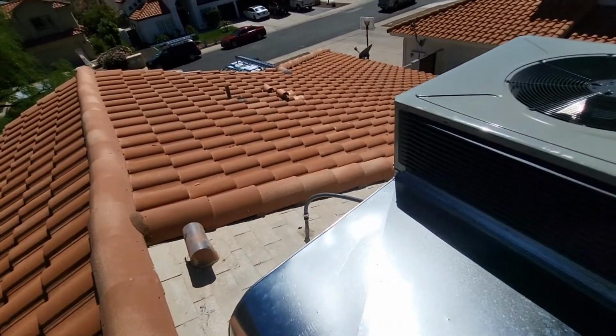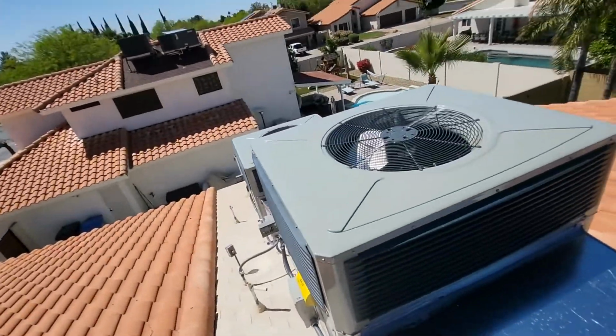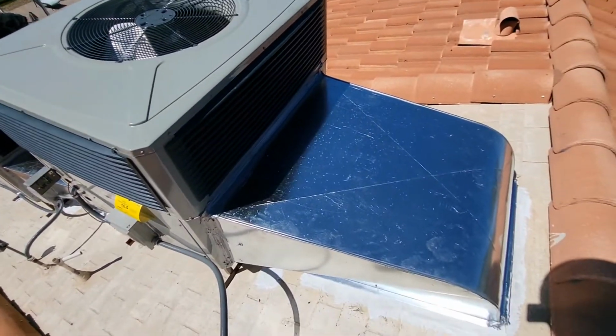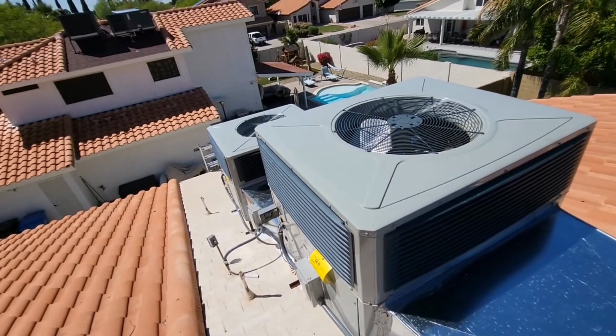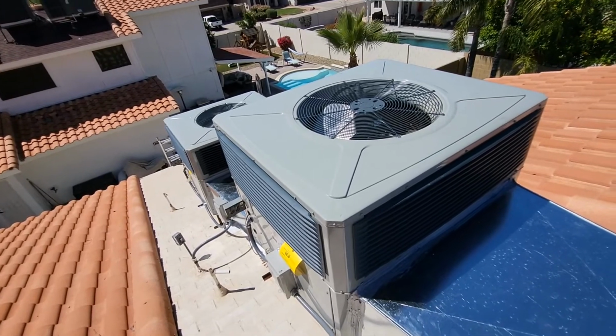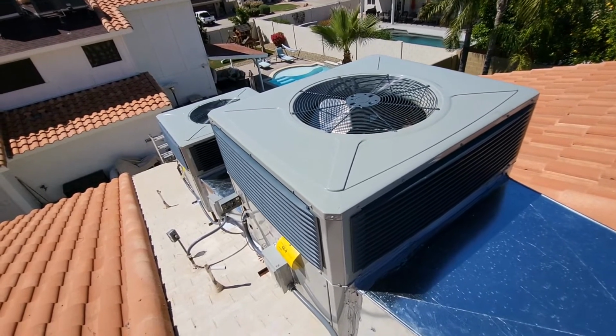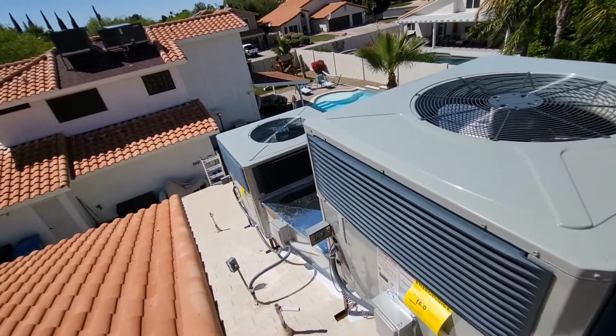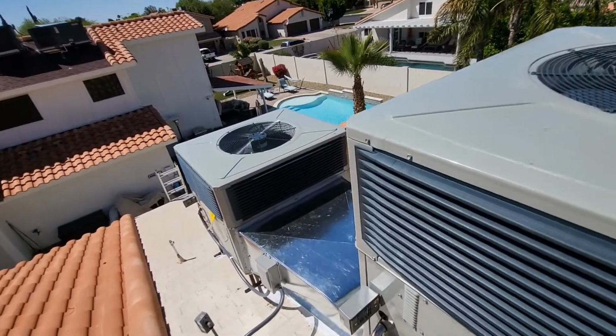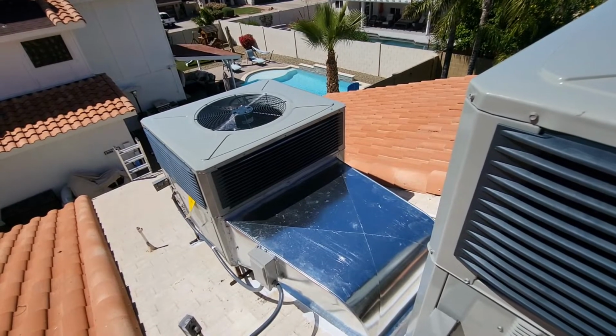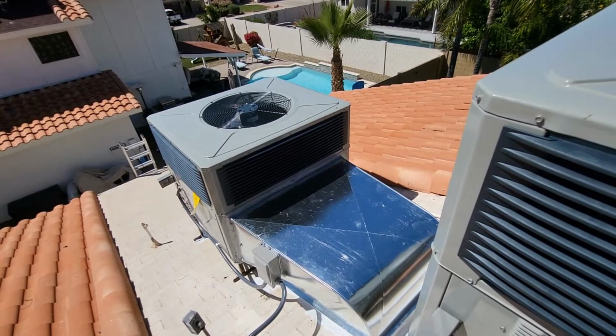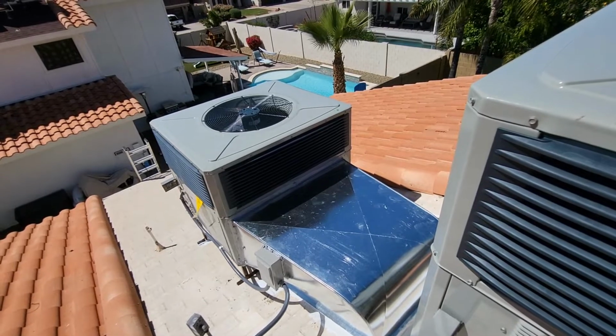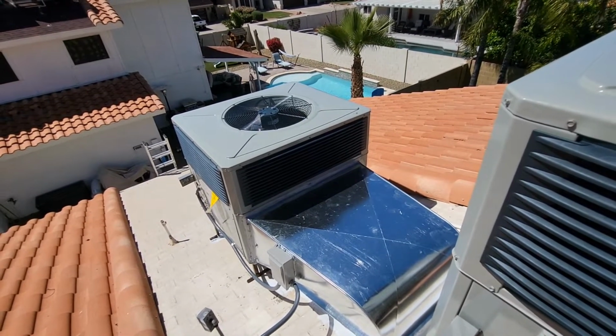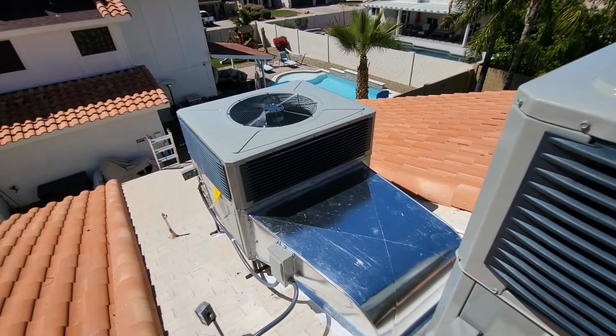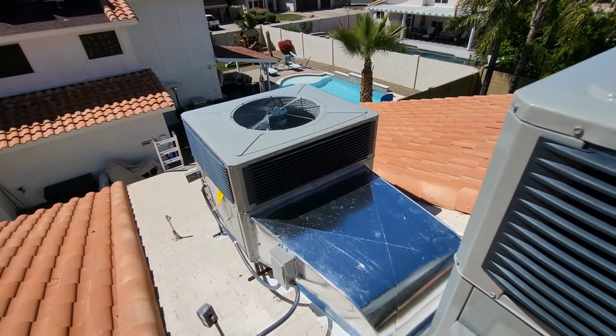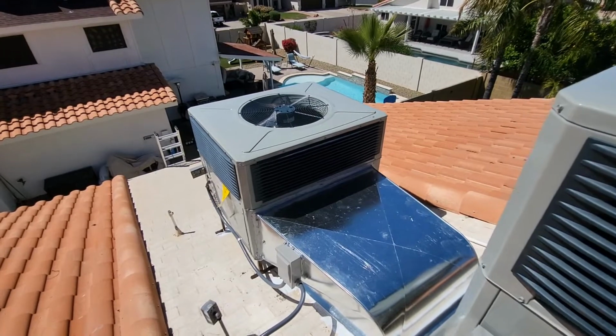So that's it. We did upsize the return, right. I'd say 90% of 20-30-year-old homes, when it's time to replace a unit, tend to not have the correct size ductwork for the new system. We did have to upsize it to 16 inch. It had 14, and according to my duct calculator, 14 would have been okay, but it would have been pushing the limits. Personally, I'd rather not risk it. So at 16, we are doing perfect.